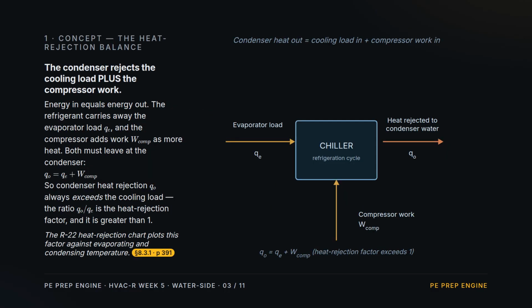Concept: the heat rejection balance. Energy in equals energy out. The refrigerant carries away the evaporator load, and the compressor adds its work as still more heat. Both have to leave at the condenser, so condenser heat rejection equals the cooling load plus the compressor work. That means the heat leaving the condenser always exceeds the cooling load delivered to the building. The ratio of the two is the heat rejection factor, and it is always greater than 1.